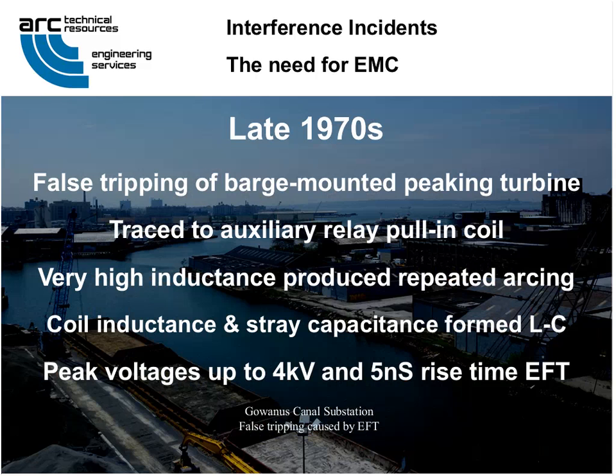Also in the late 1970s, the false tripping of a barge-mounted peaking gas turbine generator occurred. It was traced to an auxiliary interlocking relay with very low battery drain in case the plant lost power. It would go over to DC power. The relay's pull-in coil had a very high inductance, several henries, to produce a strong magnetic field with very little current. When the external circuit would attempt to de-energize the relay coil, this inductance and the stray capacitance of the control wiring created an LC circuit discharging voltages up to 4 kV DC peak on the control wiring, rise times of 5 nanoseconds or less, and repetition rates from 2.5 kilohertz or higher, as high as 1 megahertz.